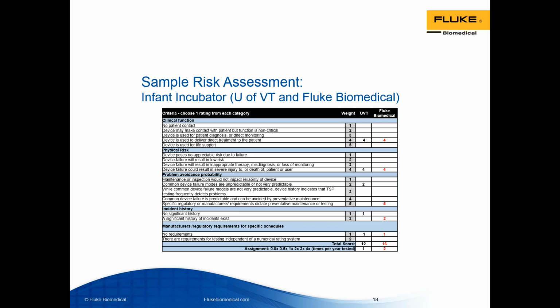So on this slide is an example of a risk assessment. One column is done by the University of Vermont, and the other in red is the Fluke Biomedical column, just to show you an example of how this can be filled out. So a combined score of 13 or more is justification for semi-annual testing, so more than once a year. A combined score of 9 to 12 is justification for just annual testing, so once a year. And then a combined score of 8 or less is justification for less than annual testing.